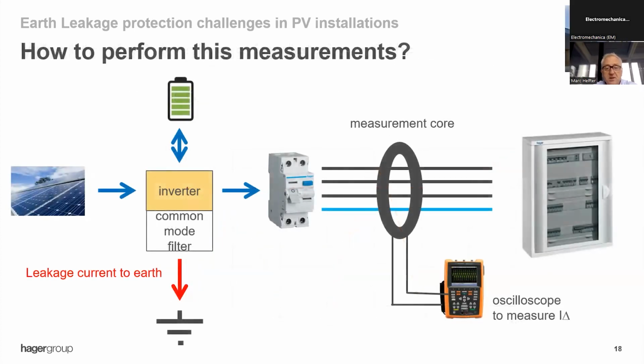So how to perform these measurements? You have to use a measurement core and put it around all the conductors, because what we want to measure is leakage. That's the sum of all the wires, the three phases and the neutral. You have to measure them together, and this will give you the residual current, in fact. And the best is to use an oscilloscope to make this measurement, to see the evolution over time, and also to have not only the current, which is the most important one, but also the voltage and frequency.